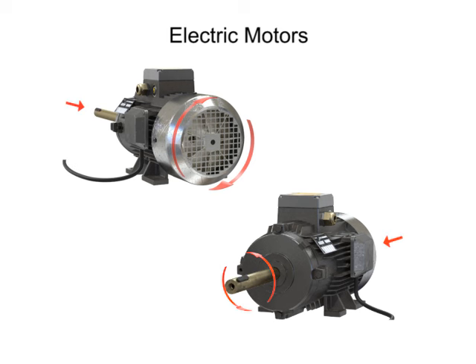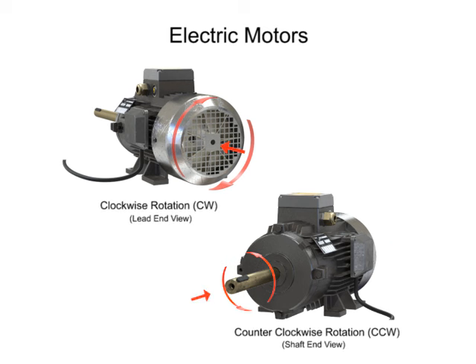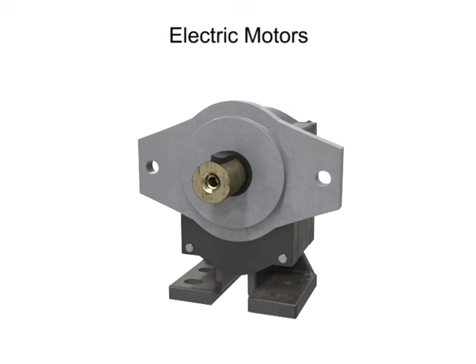In general, for most electric motors, rotation is specified as clockwise or counterclockwise when viewed from the opposite end of the shaft. This is sometimes called the lead end, since the electrical wires or leads typically connect on this end.